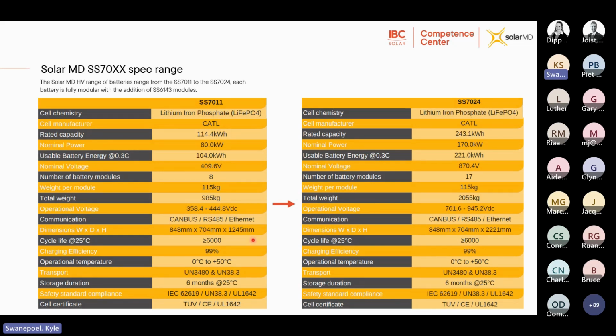I'll just note quickly, the only difference between the smallest HV battery and the biggest HV battery is actually the height. The width remains exactly the same. And then once again, because it's the same cell technology that's used in the 14.3 kilowatt hour wall mount as well as the rack mount, it's a 6,000 cycle, 12-year warranty on the battery. And then operational temperature is 0 to 50 degrees.